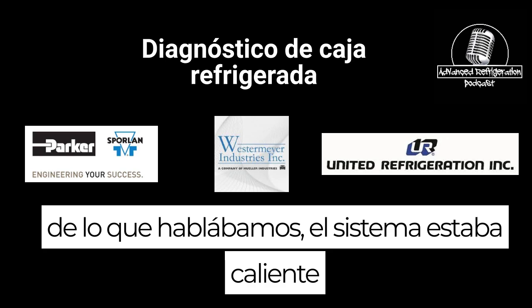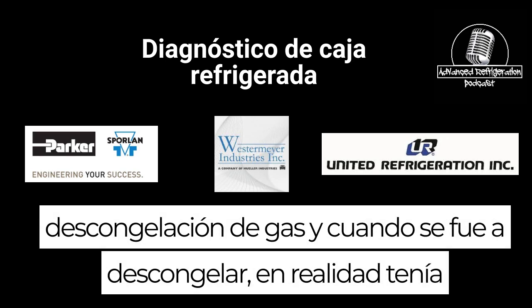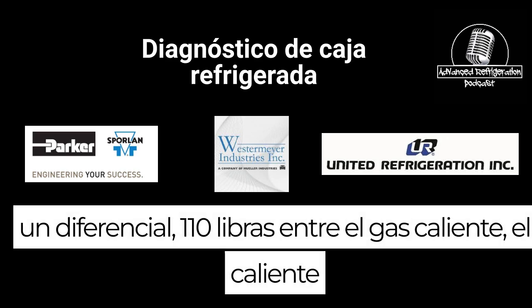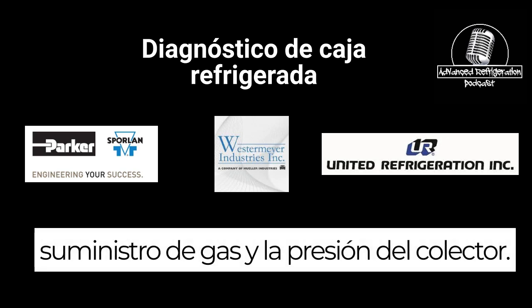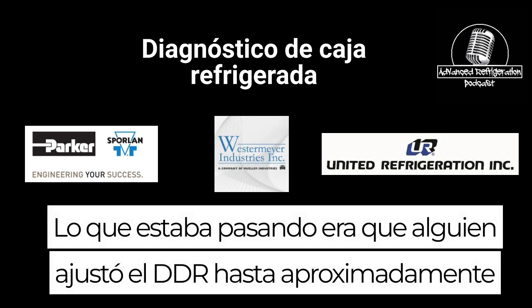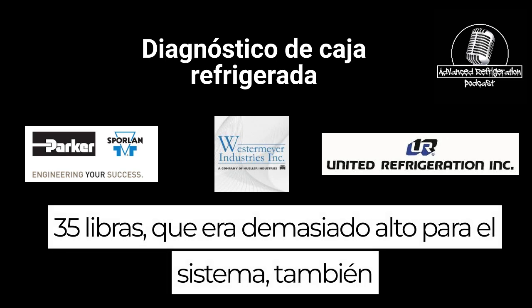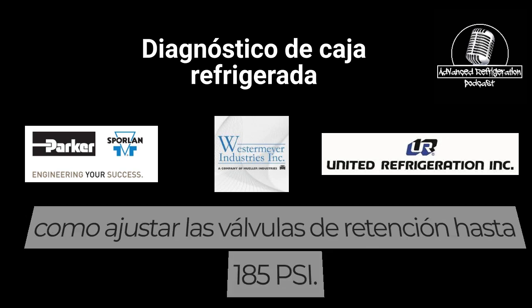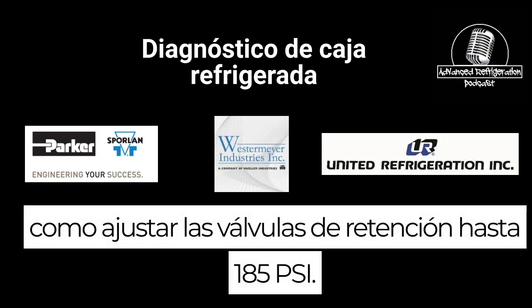the system was a hot gas defrost, and when it went into defrost, it actually had a differential of 110 pounds between the hot gas supply and the header pressure. What was happening was someone adjusted the DDR up to about 35 pounds, which was too high for the system, as well as adjusting the holdback valve up to 185 psi.